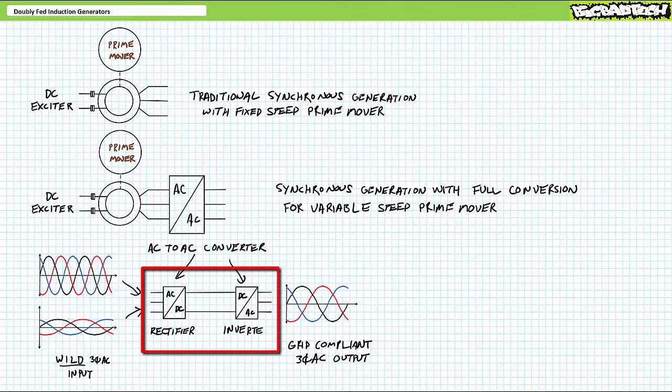For this reason, other generation methods exist that might be better suited for variable speed resources. For example, consider plain old induction or asynchronous generation. It's not the sexiest nor the smartest type of generation, but it is cheap and allows for some variability in speed. Viewers recall an induction machine driven above its natural synchronous speed can act like a generator and exports real electrical power.